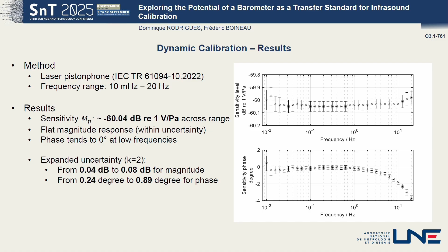Okay, so this slide is for the comparison between the static and dynamic results. As a reminder, here you have the results for the static and dynamic with the uncertainties. The sensitivities seem to be in good agreement within the uncertainties, but to check this more formally, we look at the normalized error. The normalized error is a classical performance criterion used to conclude on the consistency of bilateral comparisons.